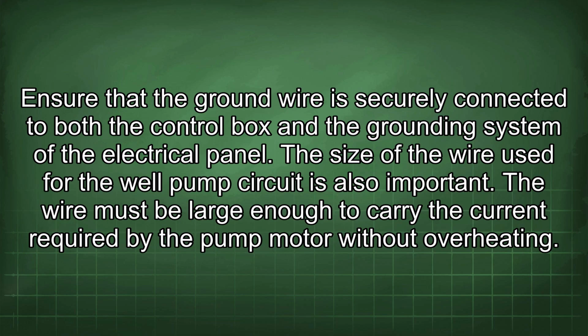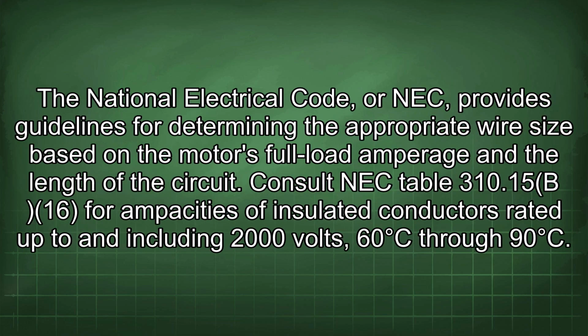The wire must be large enough to carry the current required by the pump motor without overheating. The National Electrical Code, or NEC, provides guidelines for determining the appropriate wire size based on the motor's full load amperage and the length of the circuit. Consult NEC Table 310.15(B)(16) for ampacities of insulated conductors rated up to and including 2000 volts, 60 degrees C through 90 degrees C.